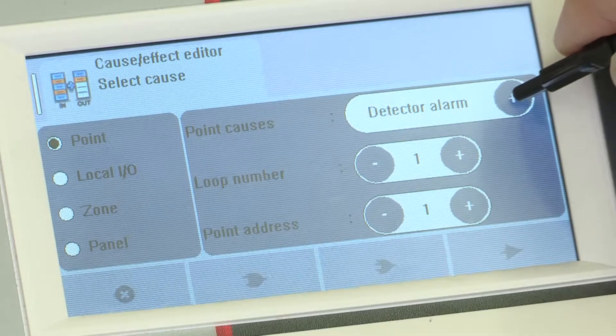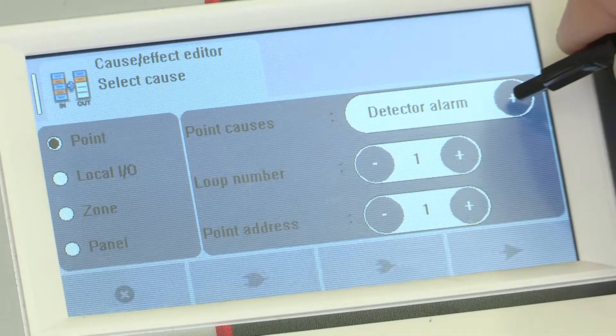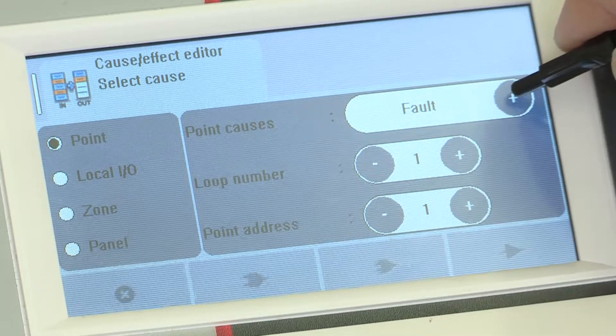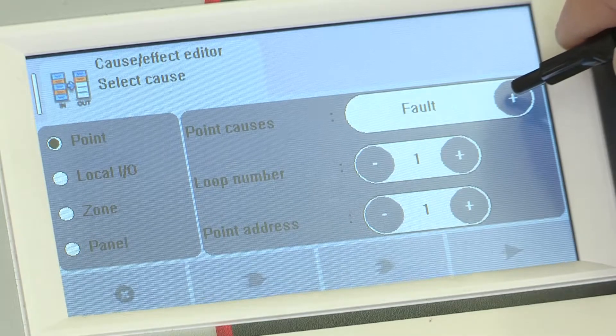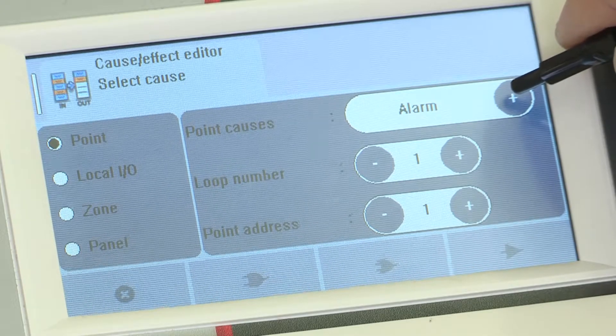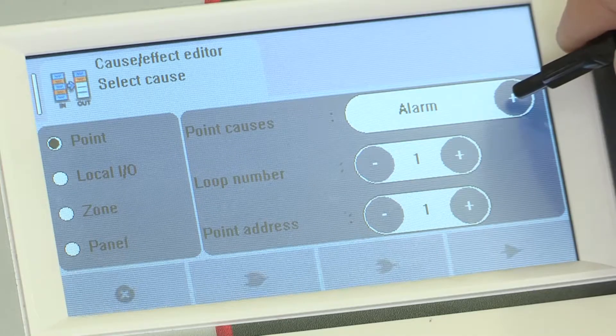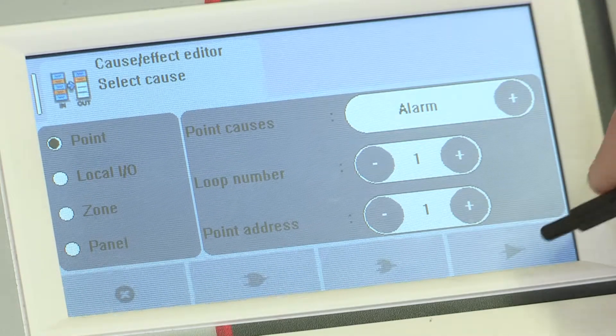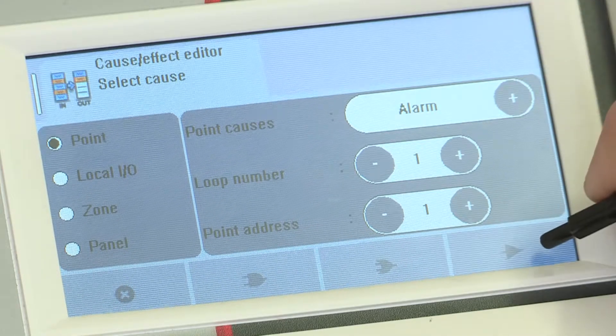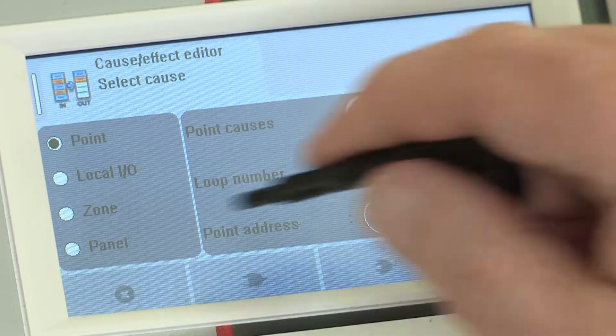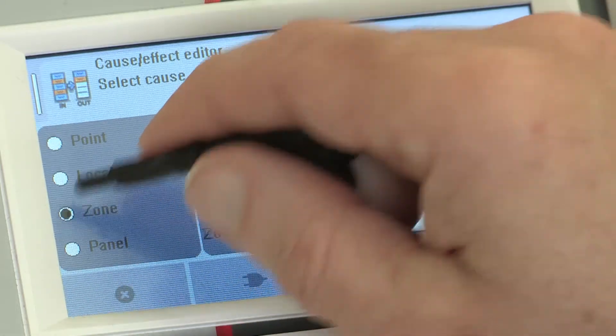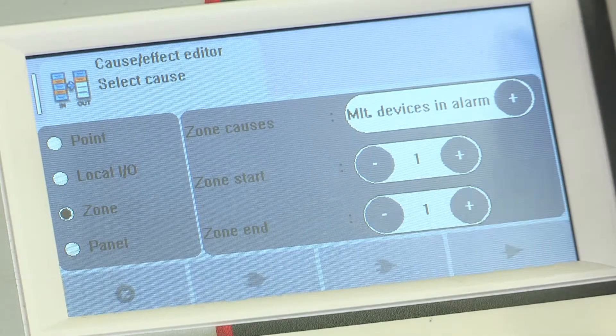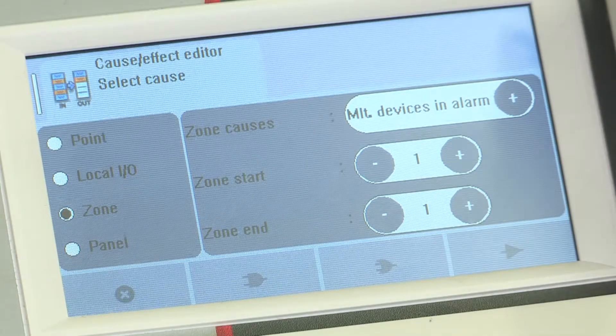The cause options include: alarm, detector alarm, MCP alarm, fault, maintenance, or tech warning — on or off where applicable. In the case of zone and panel, you also have the option for multiple device and alarm, so you can create your double knock rule.